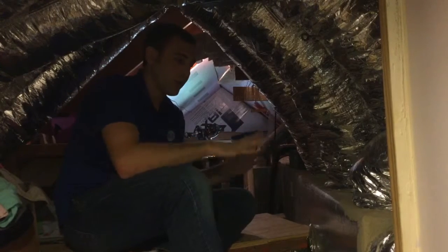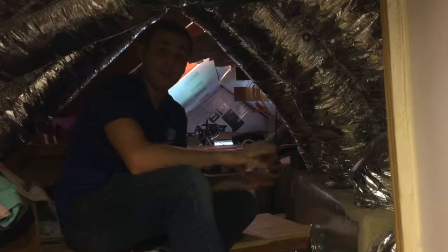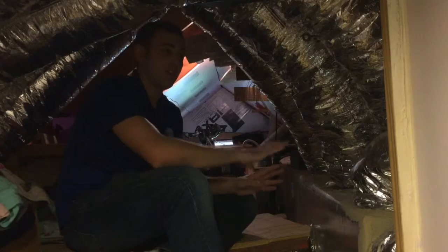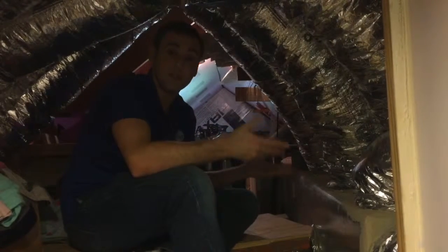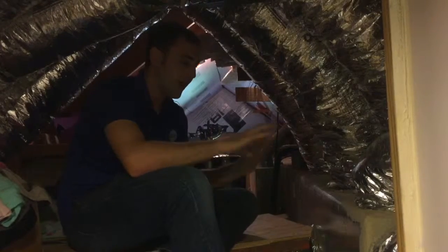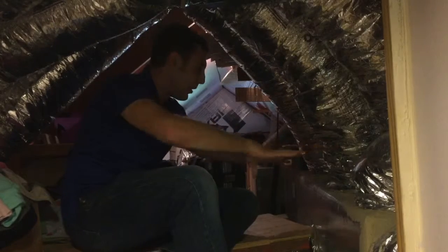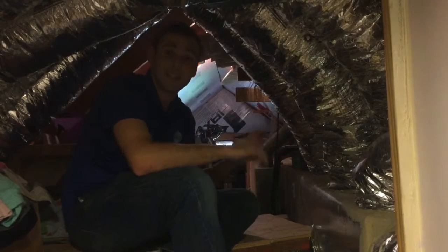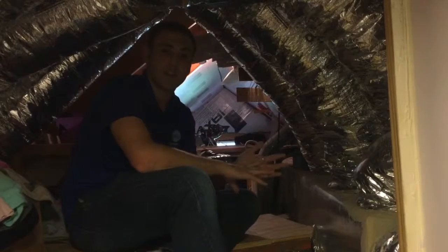But the more forethought that we can put into our buildings and really get the proper design and leave space for our mechanicals, the more efficient it's going to be, and it's also going to allow your contractor to do a better job of sealing up the ductwork, installing the ductwork correctly, that sort of thing. So providing access is another key point to the design. If I can reach every part of the duct, then chances are I'm going to be able to seal it correctly. I'm going to be able to install it without kinks or compressions or things like that.